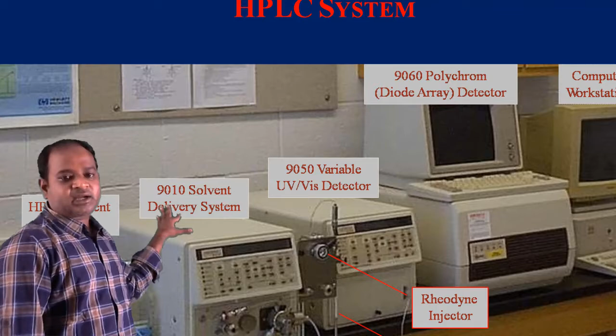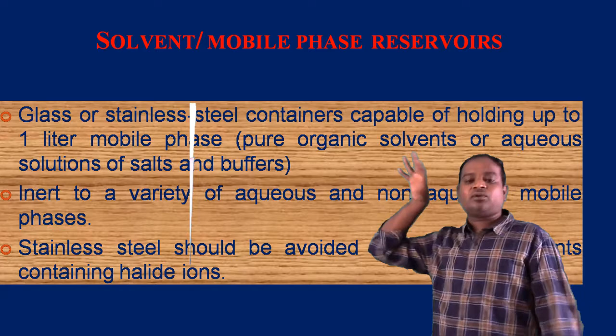Next, coming to the solvent and mobile phase reservoir. What qualities should the solvent and mobile phase reservoir have? It should have glass or stainless steel containers capable of holding up to 1 liter of mobile phase, minimum 1 liter. That should be of pure organic solvents or aqueous solutions of salts and buffers. It should be taken care of. Next, it should be inert to a variety of aqueous and non-aqueous mobile phases. That is, the container should be stable for all types of solvent chemicals. It should be inert, whether it is an aqueous or non-aqueous compound. So the glass or stainless steel container should be inert. Stainless steel should be avoided for use with solvents containing halide ions. While using it for the separation of halide ions, avoid stainless steel for the solvent reservoir as much as possible.